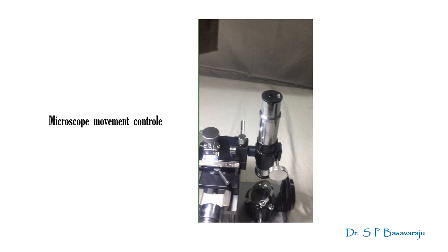Done. Now looking down through the eyepiece, the microscope is moved up slowly by turning the knob. First, what you see inside the microscope is all hazy. As the microscope keeps moving upwards, a rough image of the object begins to form. It becomes clearer and clearer and becomes clearest at some point. That's when the objective is exactly at the focusing distance from the object. Stop the movement. This is the basic procedure in focusing.